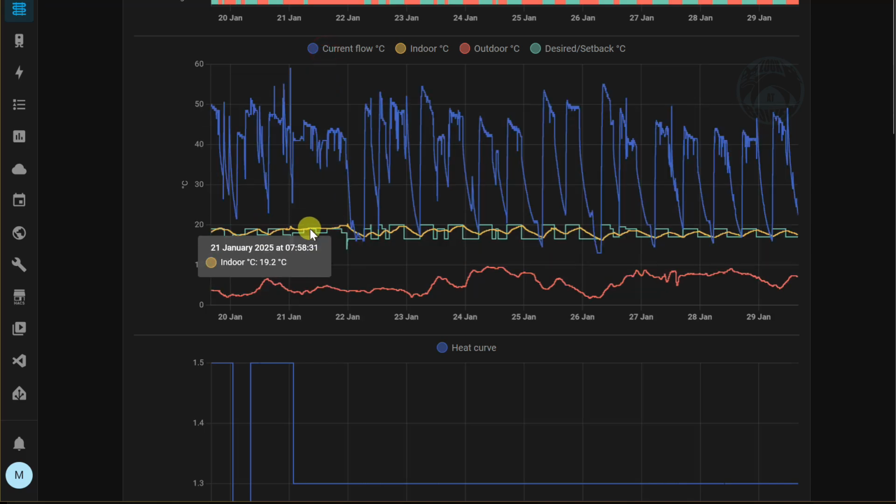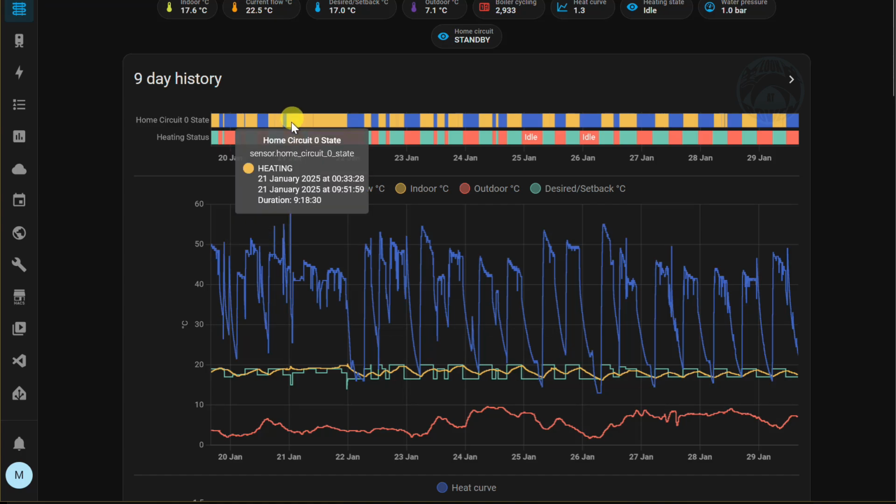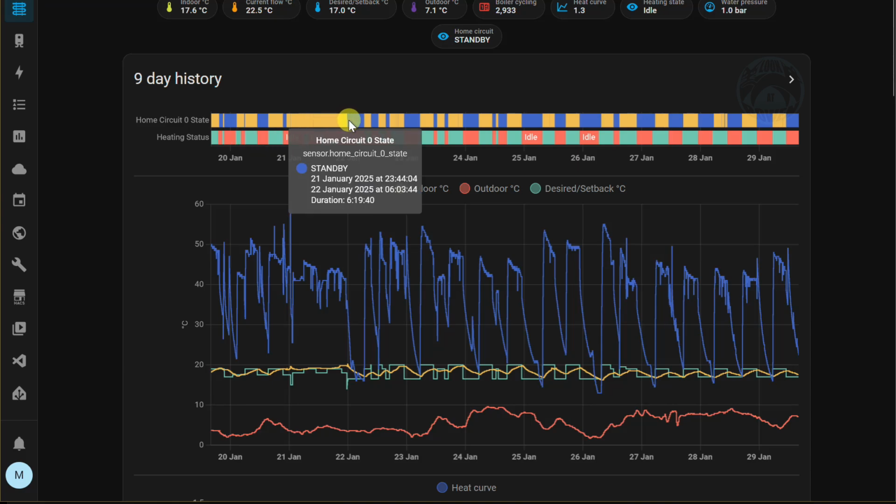So that's active. Another thing to notice with active is that the boiler doesn't switch off. And that's what it says in the manual. It just stays on and it's active. And you can see this by the circuit state graph. It's active for 24 hours, literally.